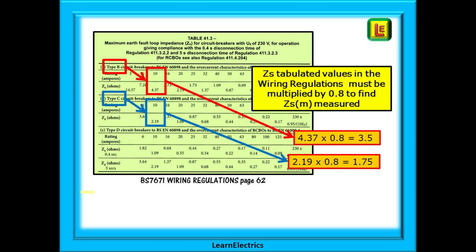The values are called tabulated values. They have come from these tables shown here. But we need measured values, something to compare our test meter measurements against. So we must then multiply these values by 0.8 to arrive at the measured values. As shown 4.37 times 0.8 is 3.5 ohms and 2.19 times 0.8 is 1.75 ohms.